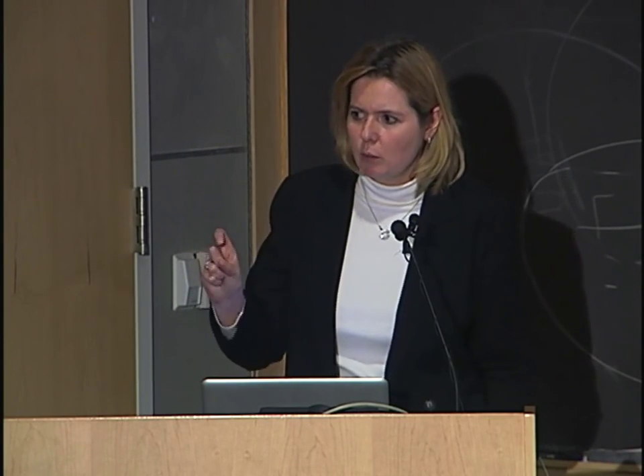I think there is one that I read about that we don't have right now that has adjustable flow, able to fluctuate the flow, let's put it that way. But the second generation devices that are constant flow are generally just set at one speed, once they find the optimal speed, and then they're left there unless there's a reason to change it. The first generation pulsatile devices would just eject blood when they filled.